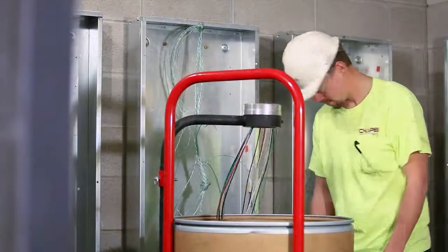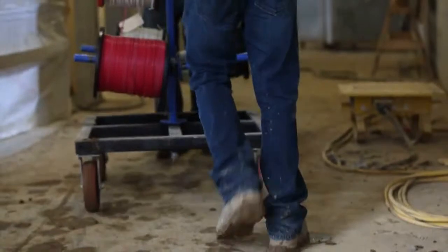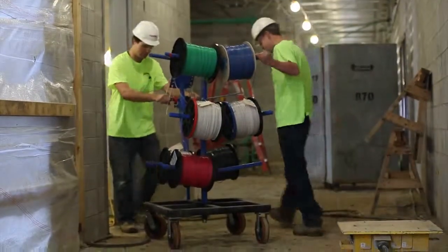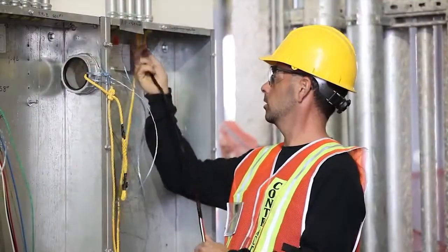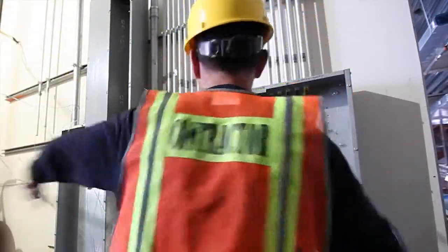You don't even have to mark the wires knowing you've got seven wires. You pull it out at the other end, you mark your wires, and you walk away. Pulling out of the barrel, it pretty well falls out — it doesn't take any effort at all. Whereas with the wire cart, you might have to really put effort into it, especially depending on how many circuits you're pulling off. You're adding more footage to your day with a lesser amount of manpower, and you're adding opportunities for these men to work without becoming overly fatigued earlier in the day, which brings them back the next day more refreshed.